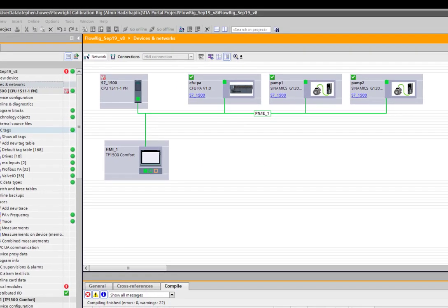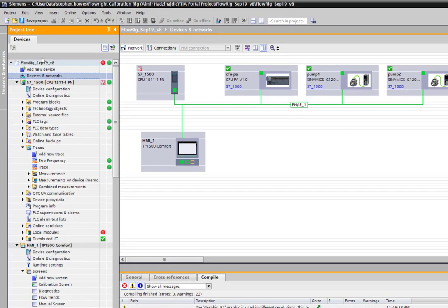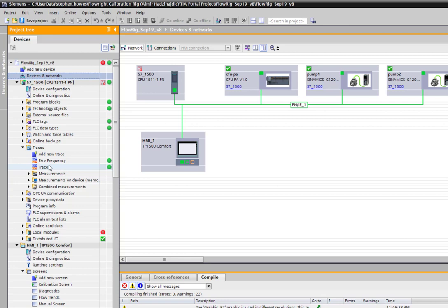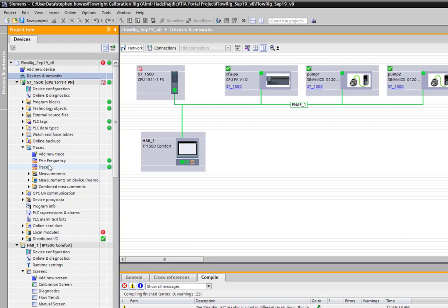The code over here is built up over time but what we're going to look at on this particular video is how well the PROFIBUS PA signal performs with regards to the high speed counter. We're not actually testing the accuracy on this because PROFIBUS PA, the value coming out of the device is actually going to be the value on the screen so there's no contamination with scaling or trimming milliamps because it's a digital signal so it's going to be accurate. What we're going to look at is the speed of response.